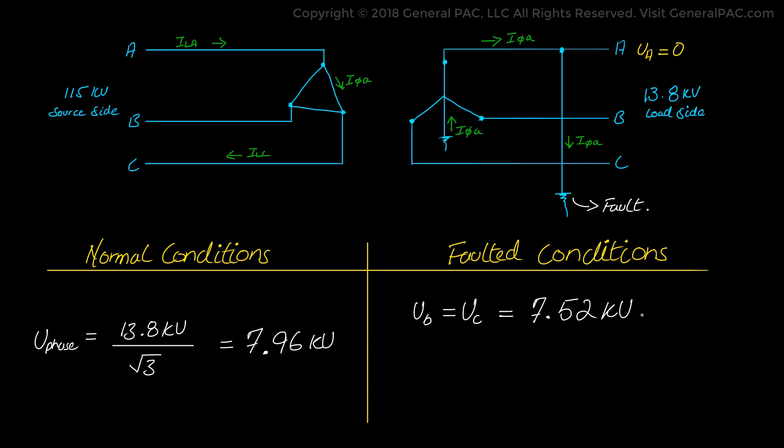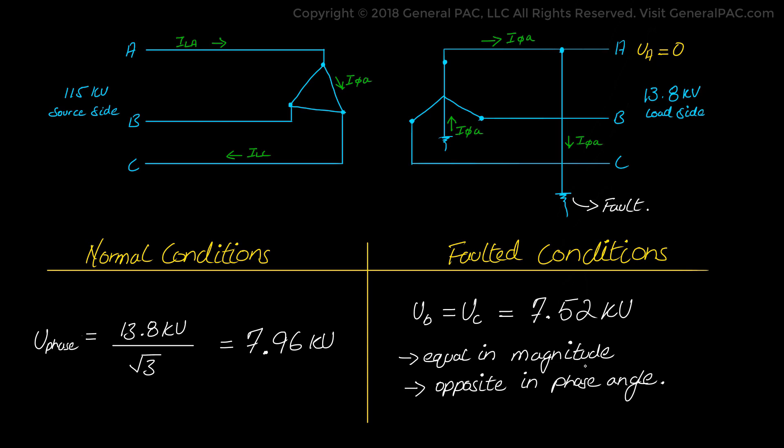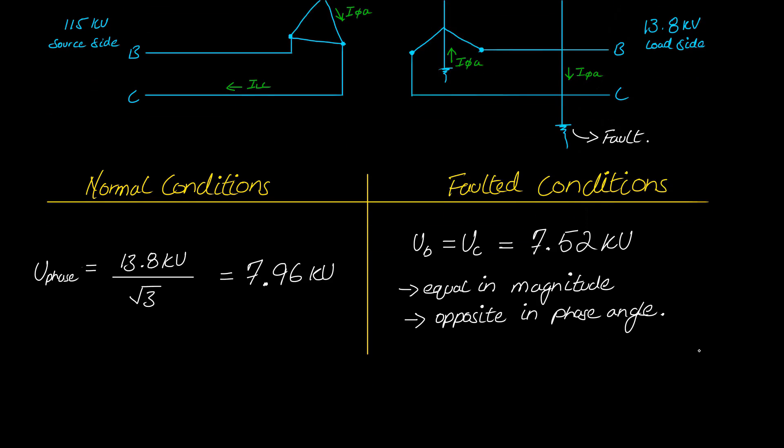Another interesting observation is that the angles of phase B and C voltages are equal in magnitude but opposite in sign — negative 113° and positive 113°. This makes sense because phase A voltage is driven to zero, and at the point of the fault the remaining two phases must balance out, so their phase voltages are equal in magnitude but opposite in angle.